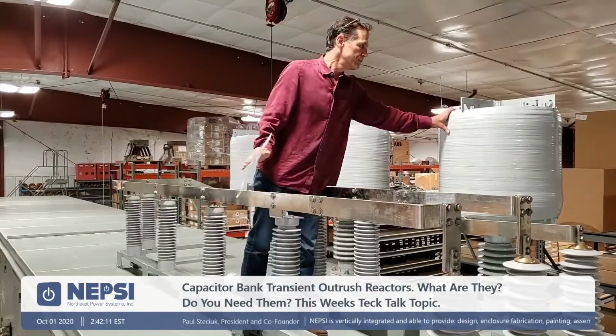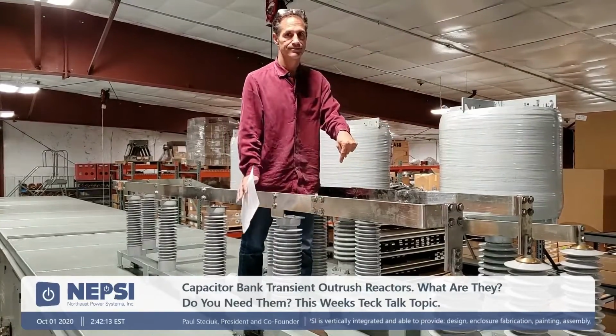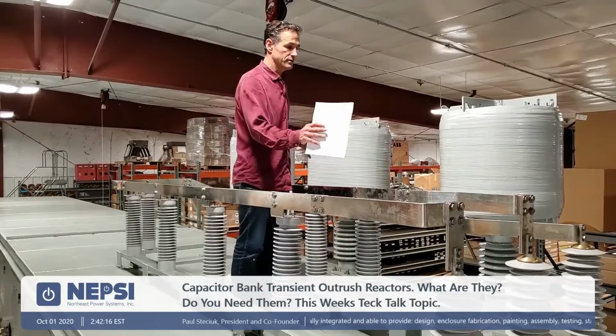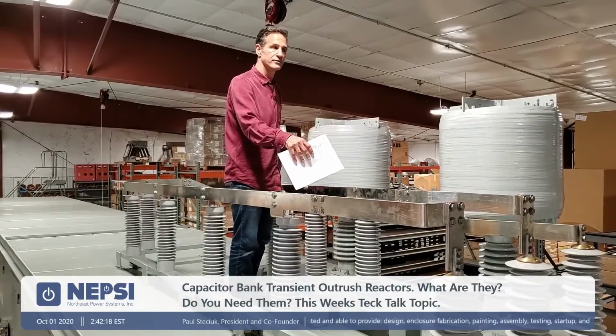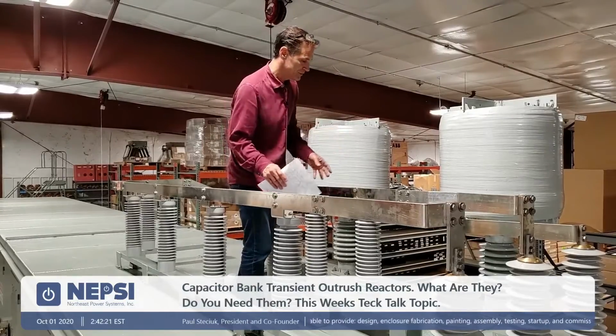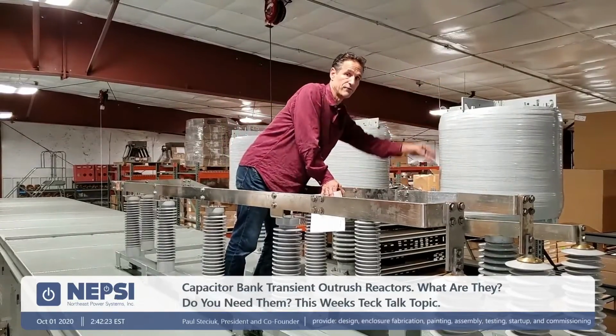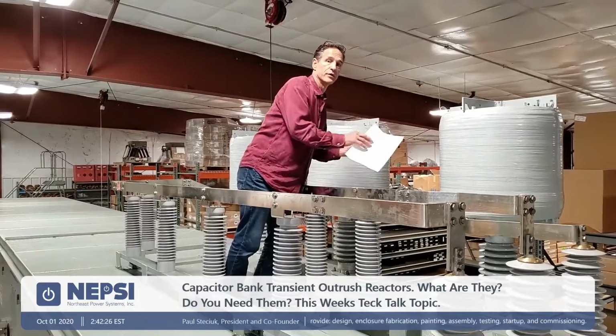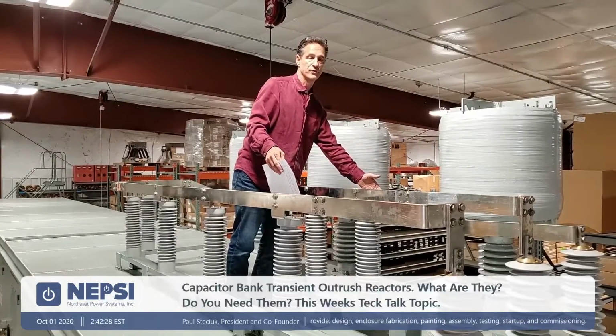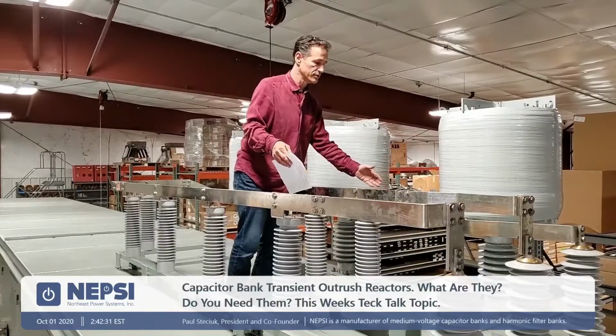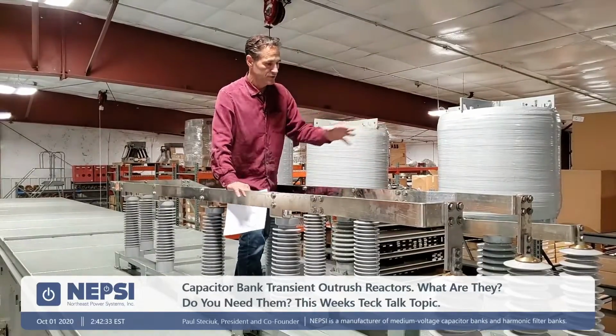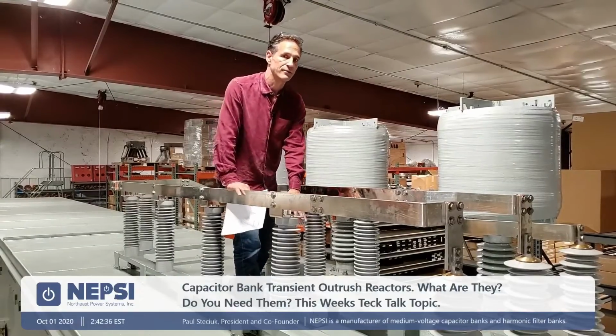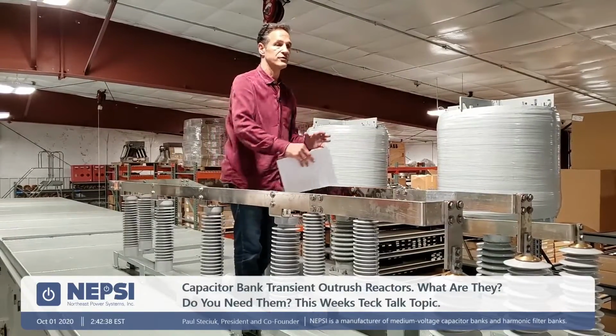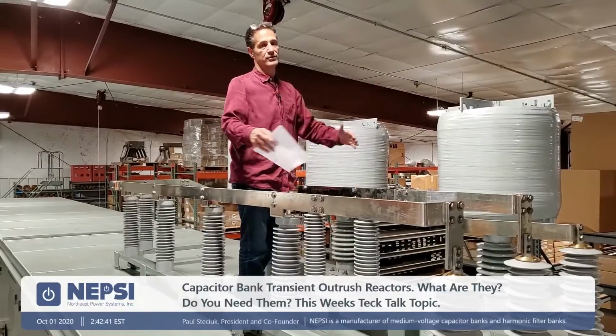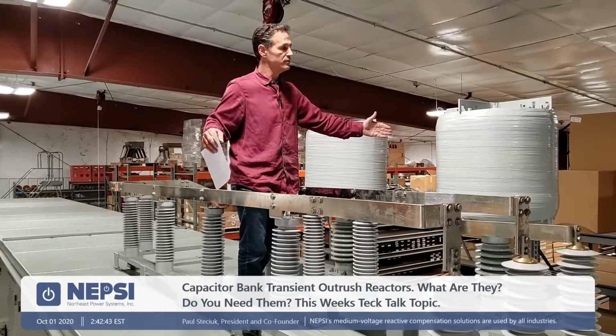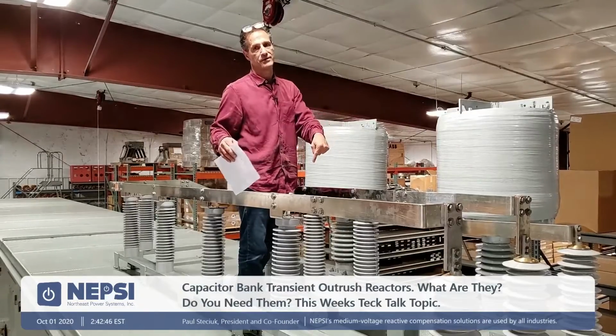Remember, we can also put these reactors inside the enclosure, and when we do that, it means that the compartment underneath has to contain these devices. And because they're air core reactors, they have a lot of magnetic field, and that magnetic field requires that we have clearance to the metal parts. So we have to make sure we don't get eddy current heating in the metal parts. So when those reactors get placed into the enclosure, we go up about 10 feet in dimension. So we're going to increase our enclosure dimension by at least 10 feet, and we sometimes have to increase the depth. But there is the ability to put these inside the equipment.